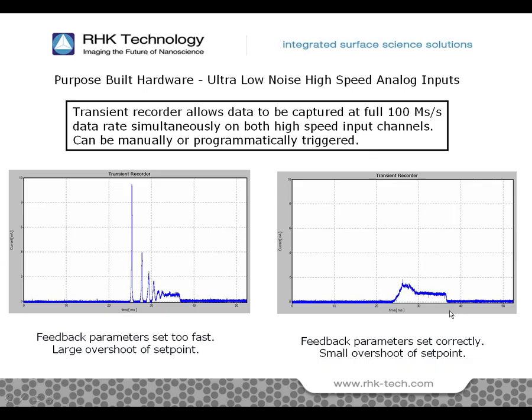This transient would be impossible to see with other systems, as the high-frequency data lasting less than a millisecond would have already been filtered out before it was even measured. With the knowledge of the first measurement, the feedback parameters can be adjusted to prevent those tip crashes on approach. With the R9 system, every time you approach, this graph will pop up automatically to display the input signal at the final moments of approach.